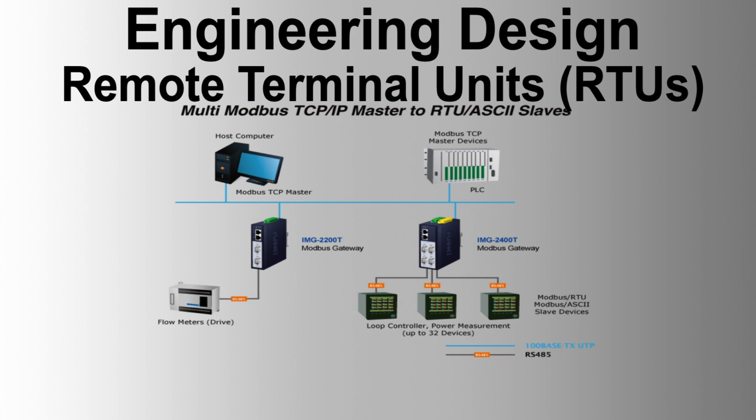Update rate. Analog input module update rate. The update rate for all hardwired analog input modules must be no worse than 2 milliseconds for all channels. Communication protocol. Report by exception, RBE. All analog inputs should follow the report by exception protocol to minimize network polling and reduce network bandwidth usage. The percentage change in value that triggers reporting should be user configurable. These requirements ensure that RTUs can handle a wide range of analog signals with high accuracy and reliability, making them suitable for various industrial applications.